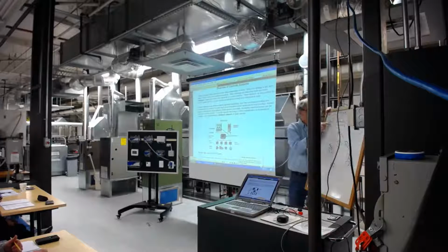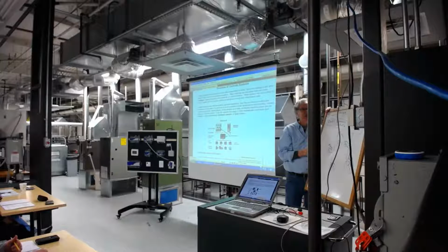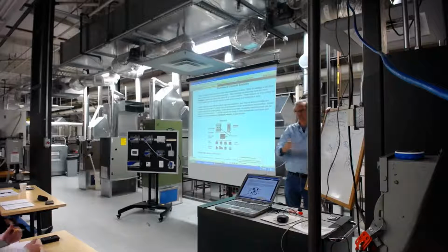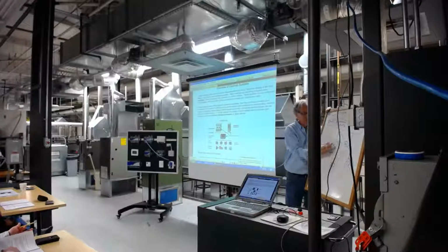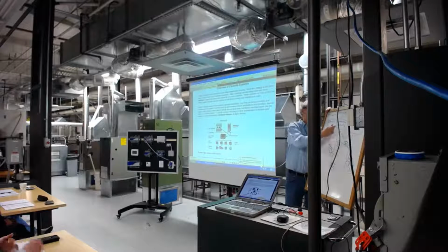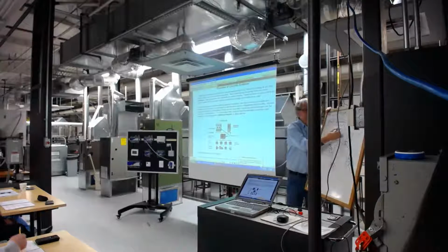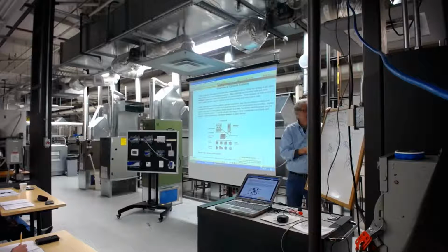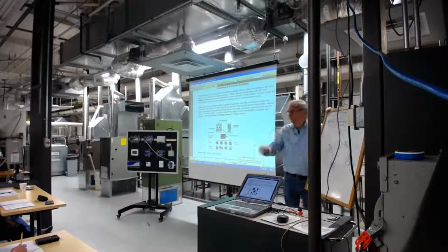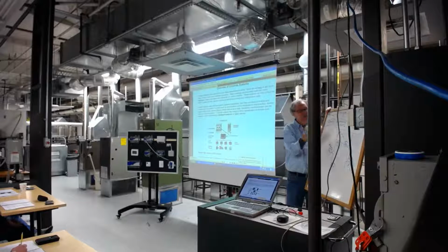Now, another thing that this thing does is long-term storage. In other words, let's say you're trending, collecting information about certain points in the system. These things are actually collecting the information, sending it back to this controller. These controllers do not have hard drives. Okay? They can only fill their buffer up so much and then they write over themselves. Or what happens is you tell these things that when your buffer is 90% full or it's midnight, upload everything to this thing. Of course, this one has a hard drive. So now you've got a hard drive collecting all this information and it's there for the long term.